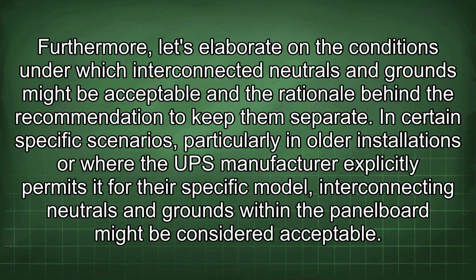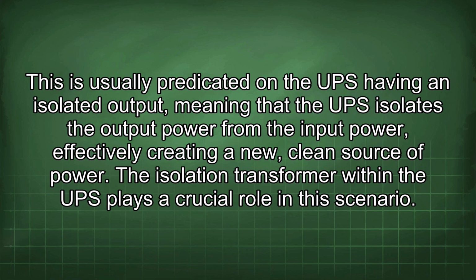Furthermore, let's elaborate on the conditions under which interconnected neutrals and grounds might be acceptable and the rationale behind the recommendation to keep them separate. In certain specific scenarios, particularly in older installations or where the UPS manufacturer explicitly permits it for this specific model, interconnecting neutrals and grounds within the panel board might be considered acceptable. This is usually predicated on the UPS having an isolated output, meaning that the UPS isolates the output power from the input power, effectively creating a new clean source of power.